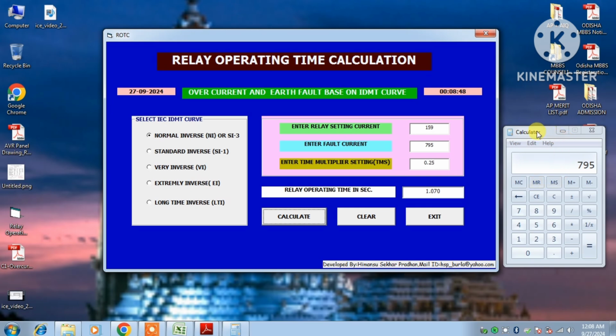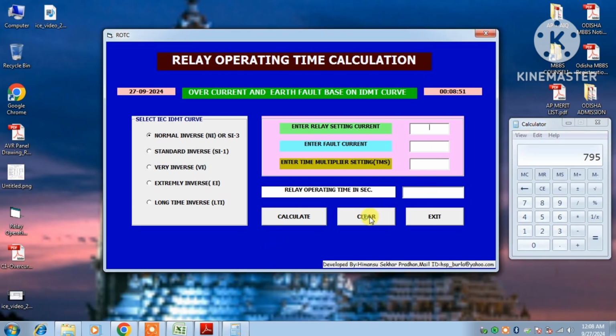So this is the utilization of this application. If you clear it, it will clear. Suppose you take a secondary value, say 0.53, and you take 5 times the fault current, 0.53 into 5 times, that is 2.65. I will enter 2.65 here, and the TMS value is given as 0.25. If you calculate it, it will operate in 1 second. So this is the utilization of this application.